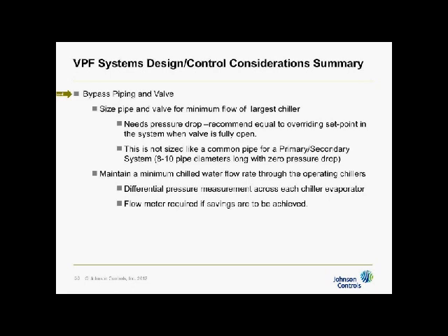Whatever the largest chiller is what you size it for. And it needs a pressure drop. We usually recommend that when you're down to a minimum flow condition, there's hardly any resistance head left in the whole system. The only thing that's left is practically the set point at the end of the circuit. So if you size the pressure drop with the bypass valve fully open to be the same as the set point, you'll be able to get good controllability. You can move water through the bypass or out to the system very easily.